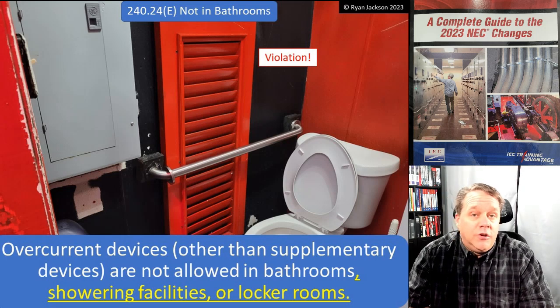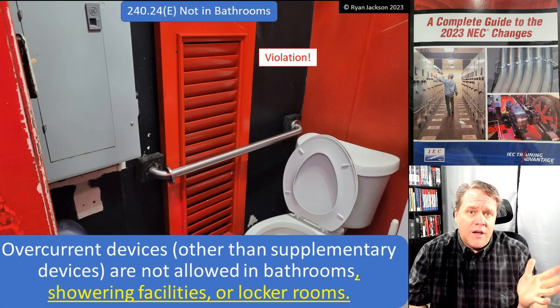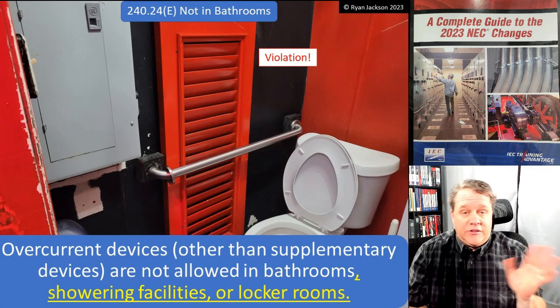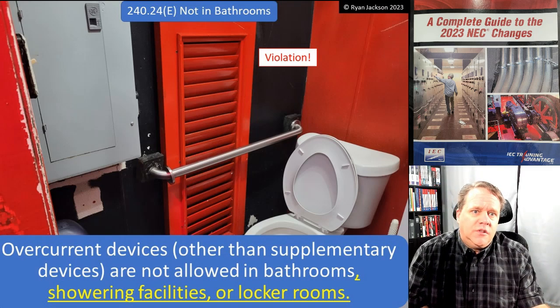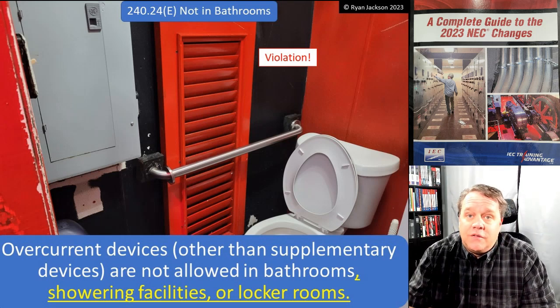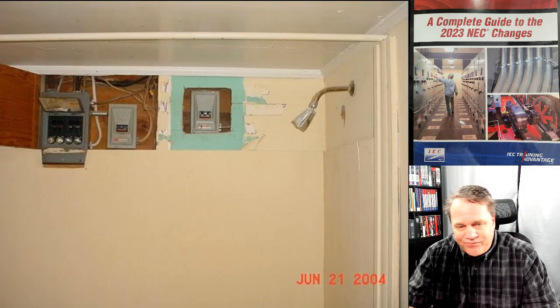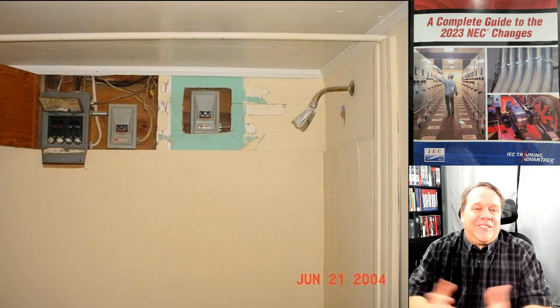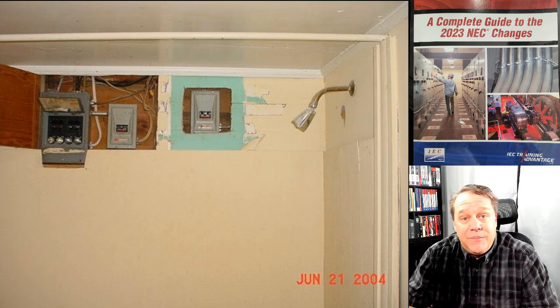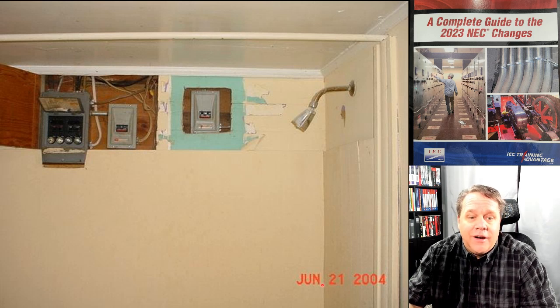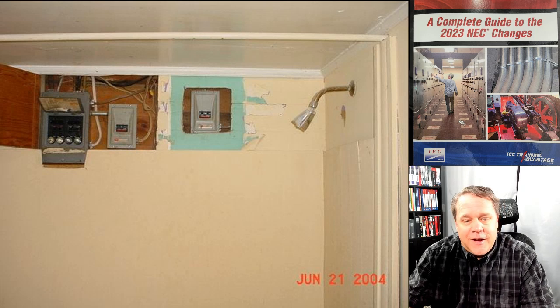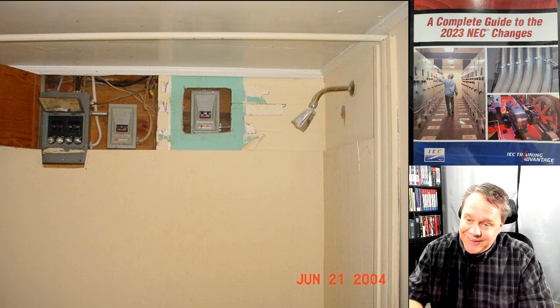Overcurrent devices like these are not allowed in bathrooms, showering facilities, or locker rooms. This picture was a bathroom in New Orleans — it complied when it was installed, it complied when I took the picture, but it would not comply today. That doesn't mean you have to rip it out; it just means you couldn't install it there today.